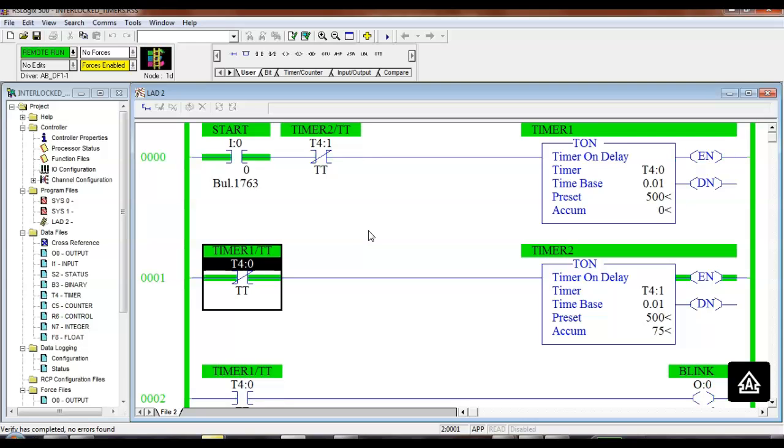These are cycle timers. So if I wanted something to happen in a cycle, then this is the way we would do it, right? You understand that? We just interlock these 2 timers, but you got to be able to understand why we do not cross couple, because what we're doing is one of them's energizing the other. When it gets through, it energizes the other one. It stops timing, energizes the other one. It starts timing, right? And you set that clock and does what? Goes back and forth.